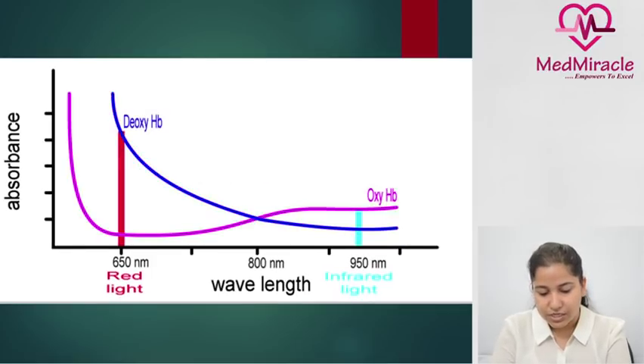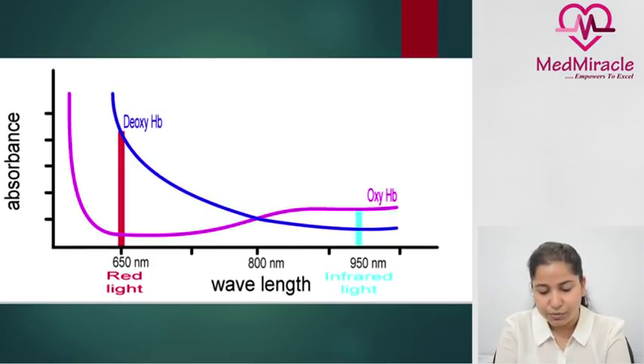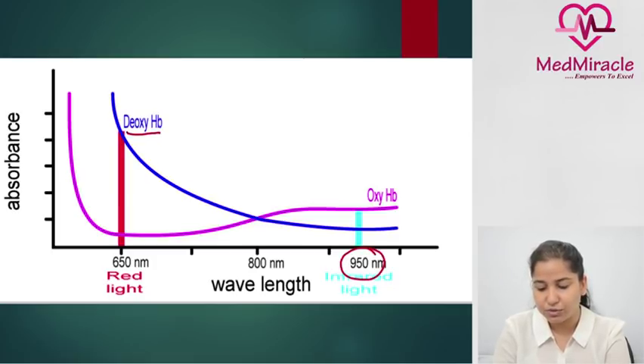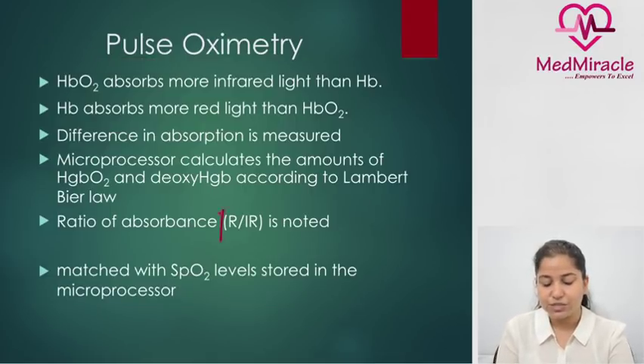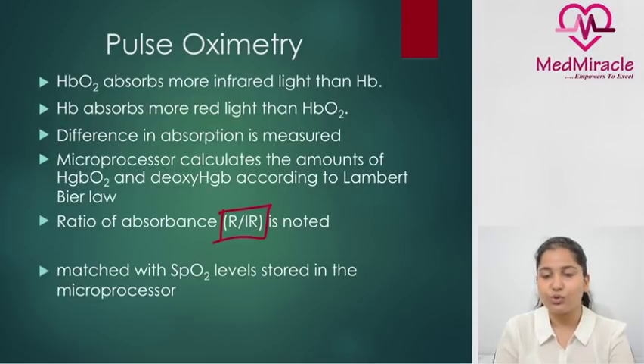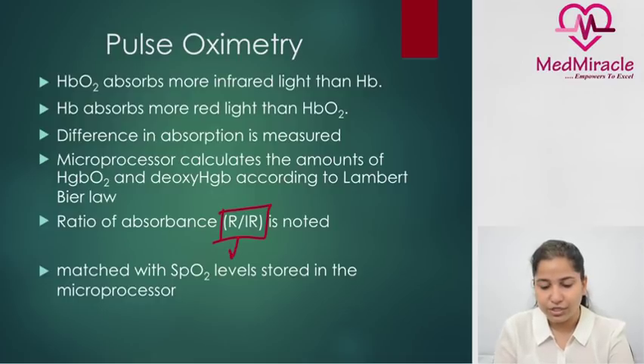Deoxyhemoglobin has higher absorption for red light and oxyhemoglobin has higher absorbance at 950 nanometers. The ratio of absorbance of red to infrared is noted and matched with SpO2 levels stored in the microprocessor, and whichever value matches is shown on the monitor.